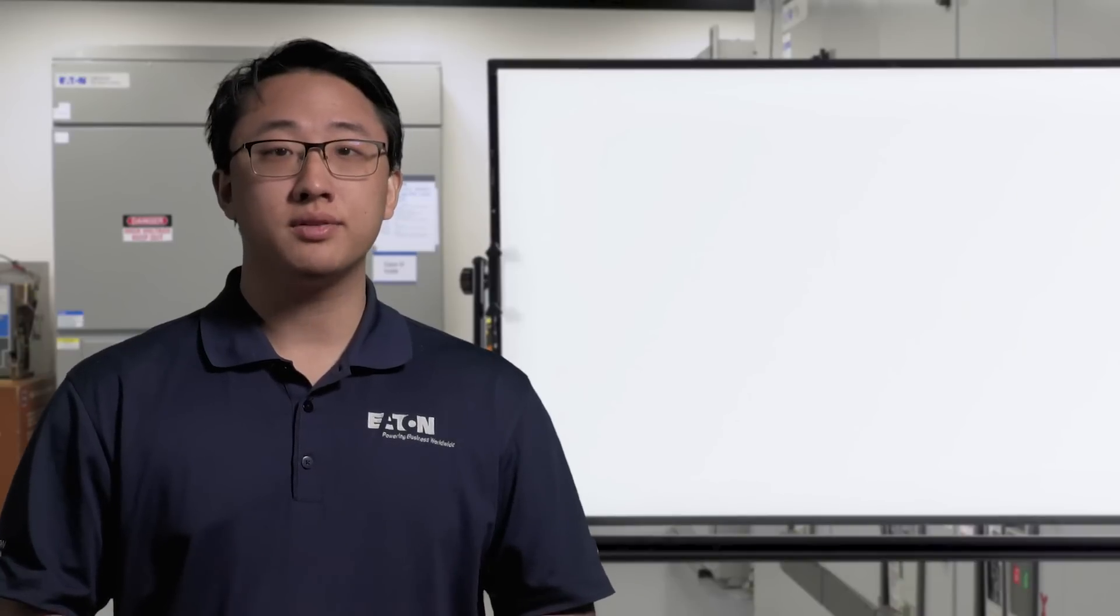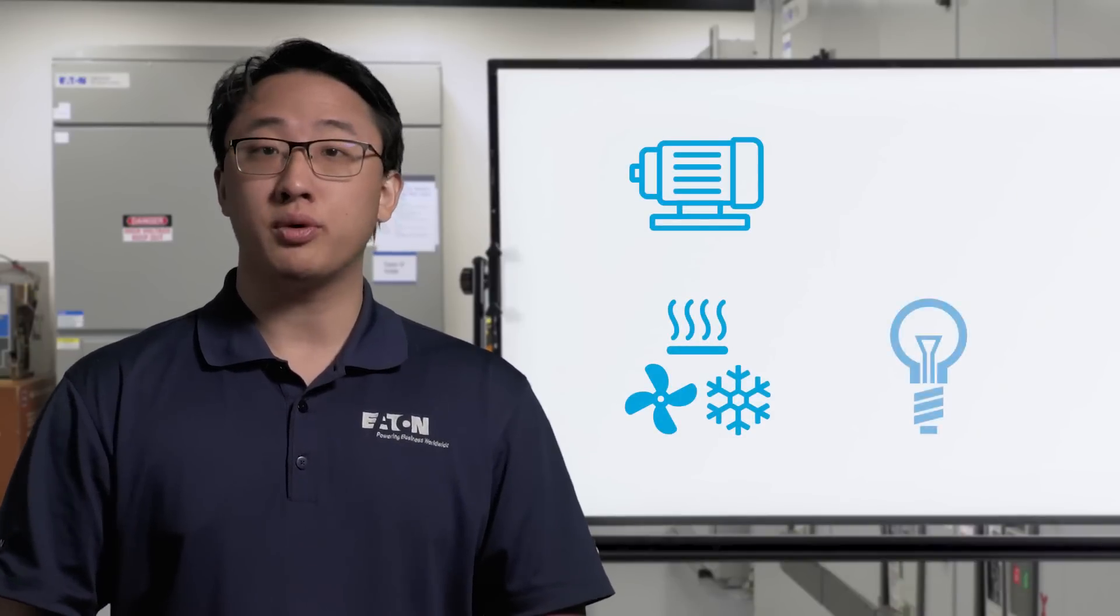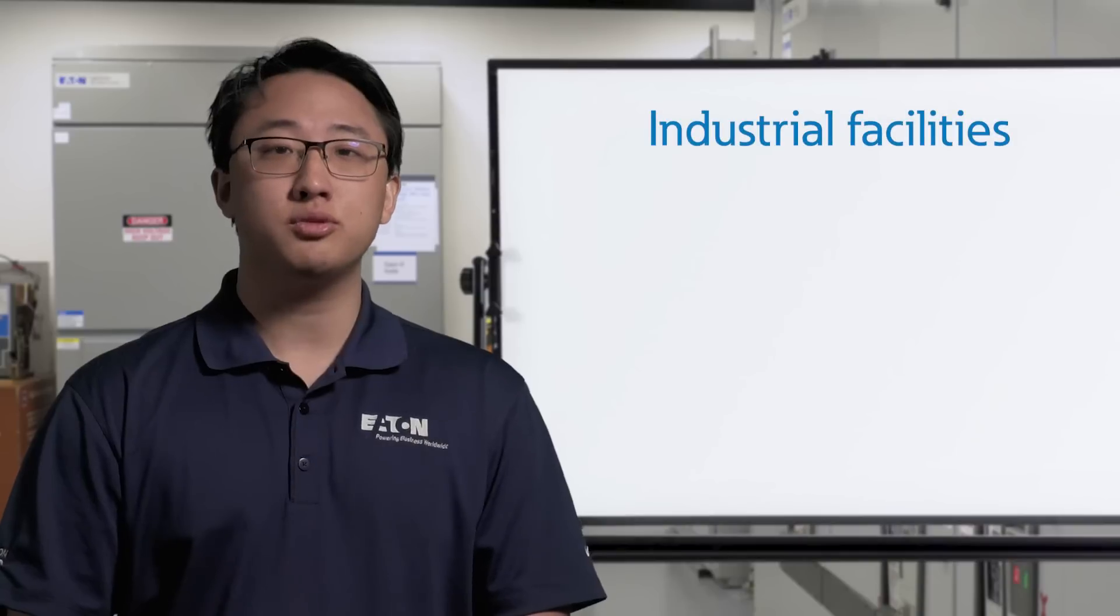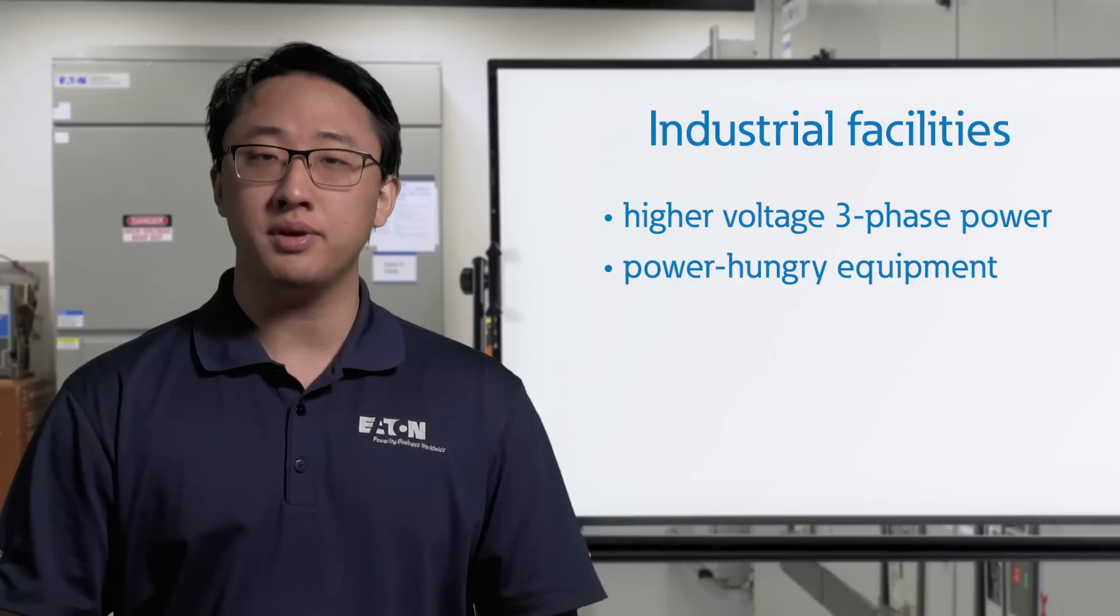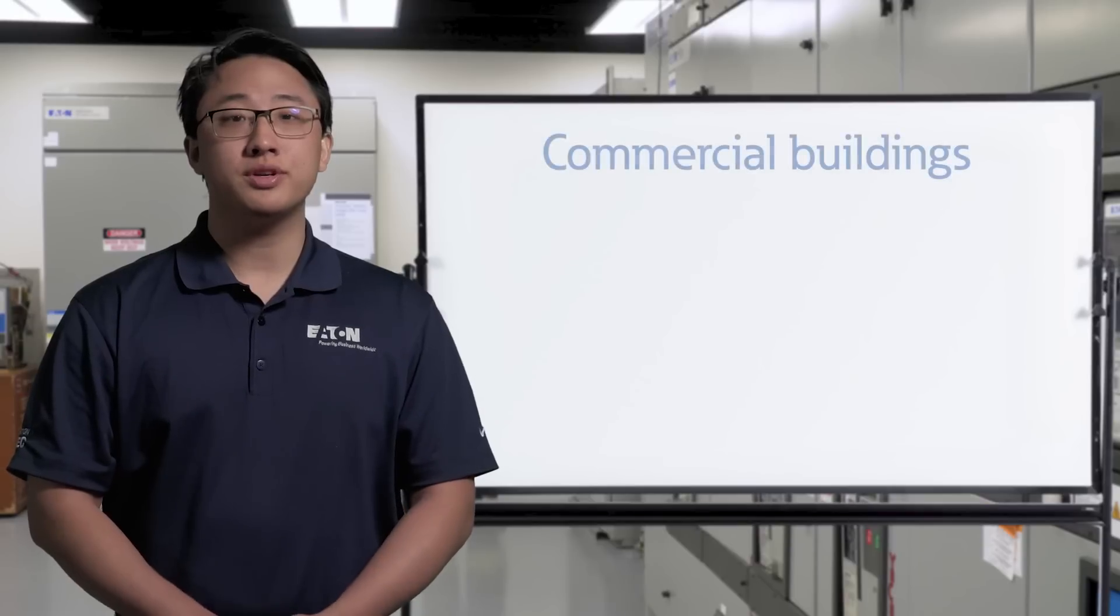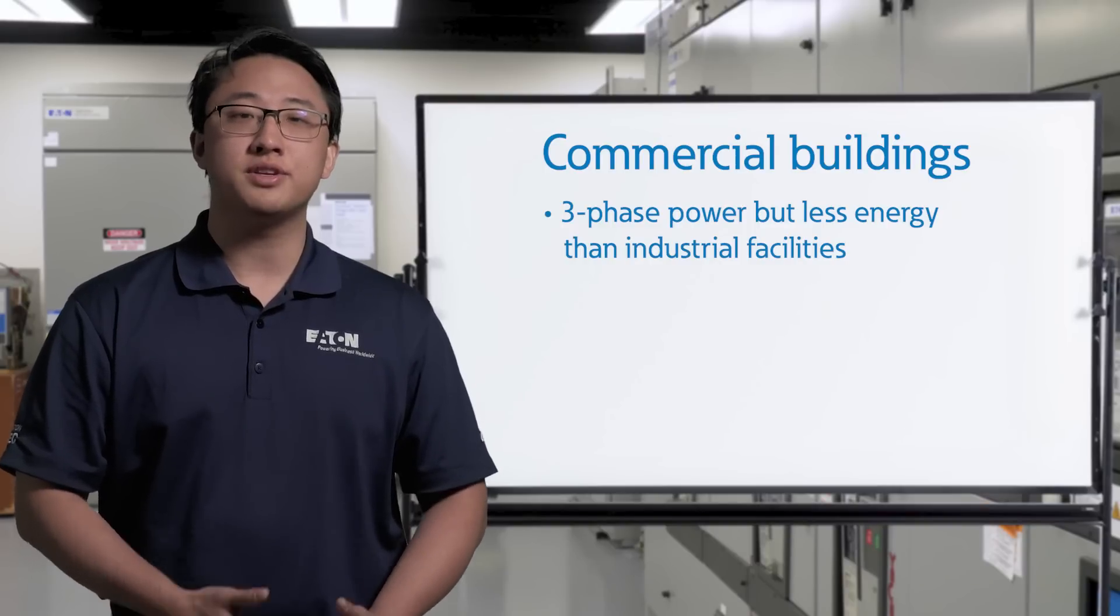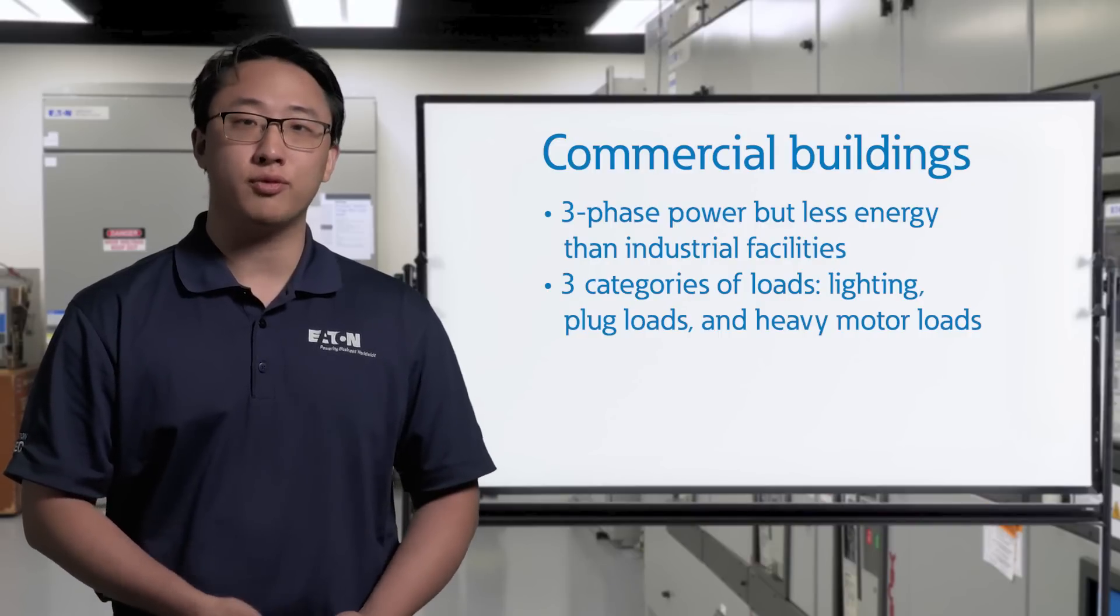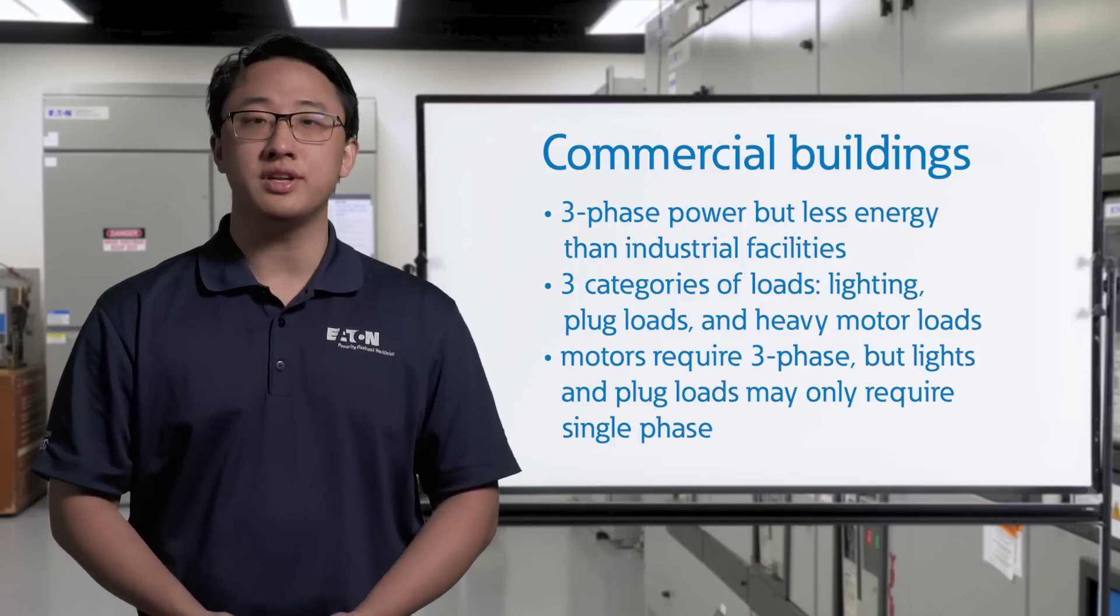Depending on the application, loads will require different voltage levels. Some require three-phase, some require single-phase, and still others may require a combination of both. In industrial applications, facilities will be designed for higher voltage three-phase power. This feeds many different types of power-hungry equipment, 70-80% of which are three-phase motors. Commercial buildings also run on three-phase power, but they usually draw less energy. Loads are broken up into three even categories: lighting for the whole building, plug loads like everyday electronics, and heavy motor loads for functions like HVAC. The motors will require three-phase, while lighting and plug loads only need single-phase.